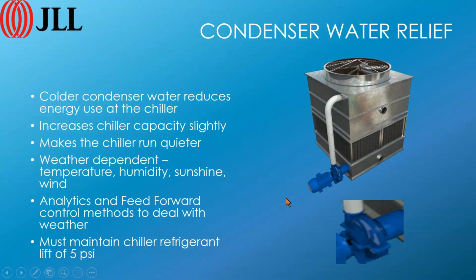Now down at the bottom, you'll see a little square there with a pump. We also control pump speed to make sure that you have enough pressure inside the condenser to push the refrigerant out and through the expansion valve. When the cooling tower water temperature drops, the refrigerant pressure drops down. When that occurs, we slow the pump down. By slowing the pump down, that brings the pressure back up. So there are two things happening. The pump is making the pressure go up, and the cooling tower is making the temperature of the refrigerant drop down. Those two are getting closer and closer together, closer to the saturation point.